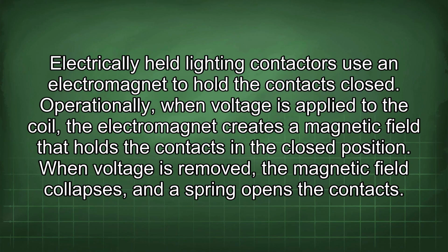Electrically held lighting contactors use an electromagnet to hold the contacts closed. Operationally, when voltage is applied to the coil, the electromagnet creates a magnetic field that holds the contacts in the closed position. When voltage is removed, the magnetic field collapses, and a spring opens the contacts.